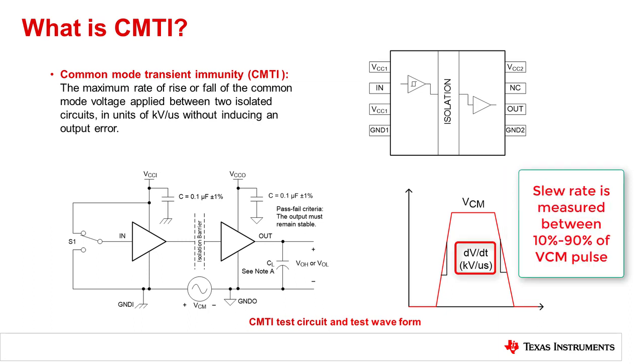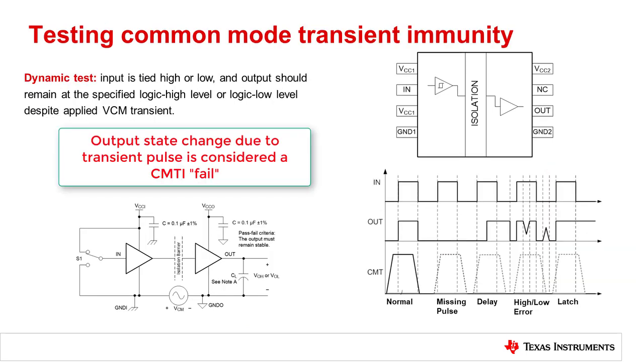The digital isolator reinforced standard VDE 0884-11 recommends measuring the slew rate of the common mode pulse calculated from 10% to 90% of the final common mode pulse. Because the output of the digital isolator only supports digital data, a state change due to common mode transients would be considered a CMTI fail, which would mean a change from Vout high to Vout low or Vout low to Vout high under the influence of the transient.